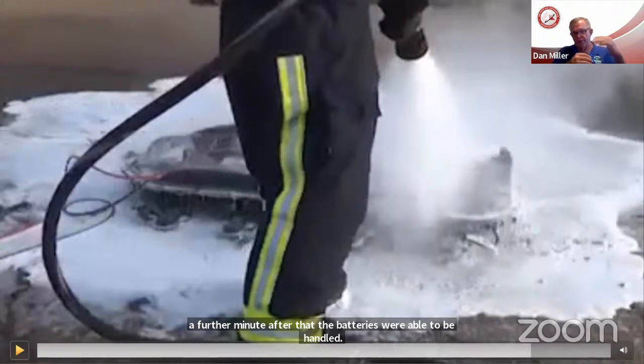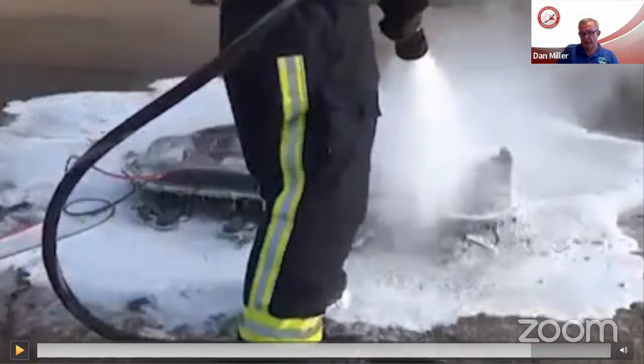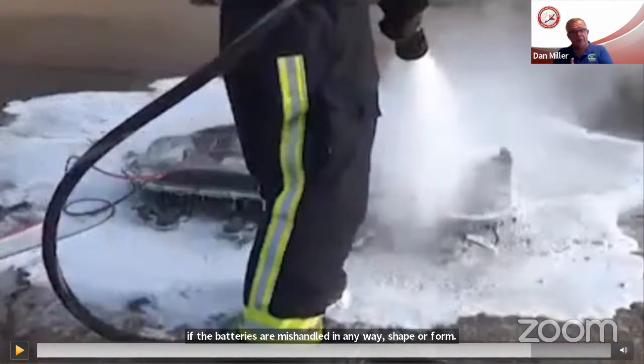One of the things that often comes up as we discuss lithium-ion batteries is reignition. Reignition can occur—it doesn't often occur after we apply F500—but if the batteries are mishandled in any way after they're extinguished, they can have a new or reoccurring short circuit internally and go right back into thermal runaway. So mishandling post-fire is one of the big reasons for reignition.